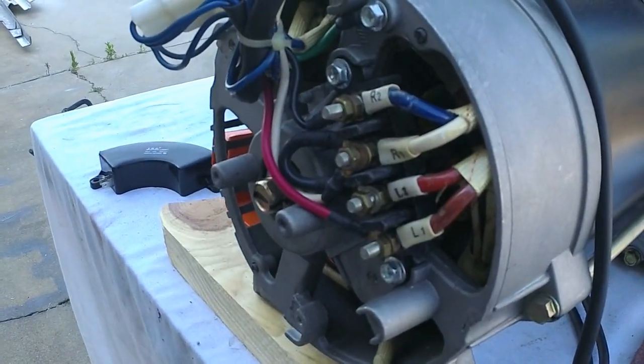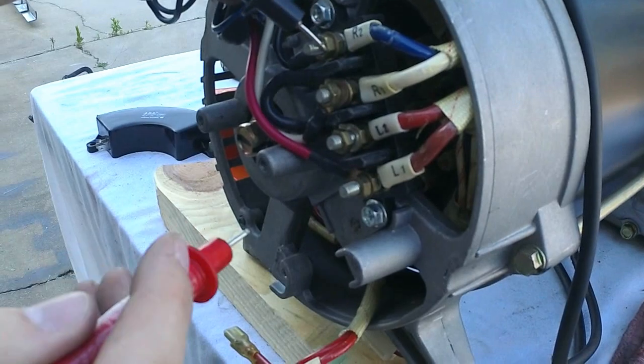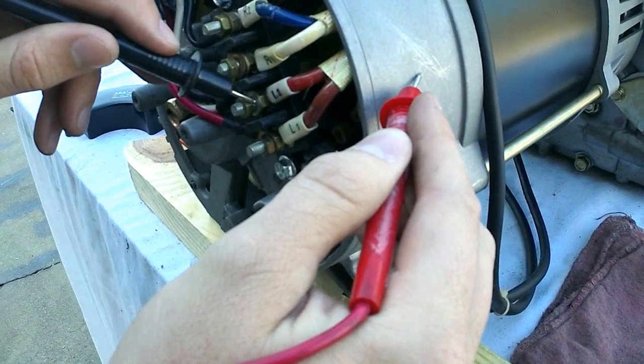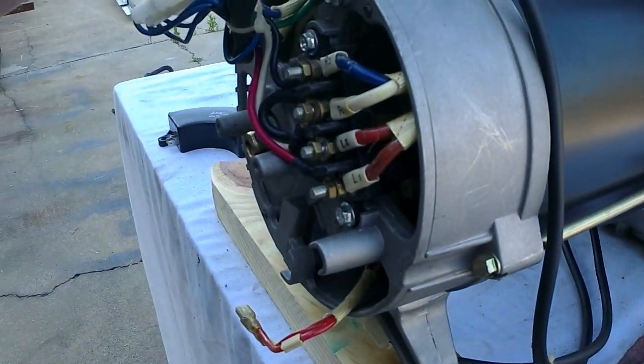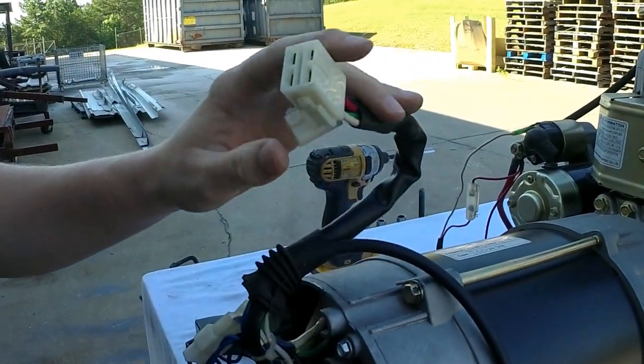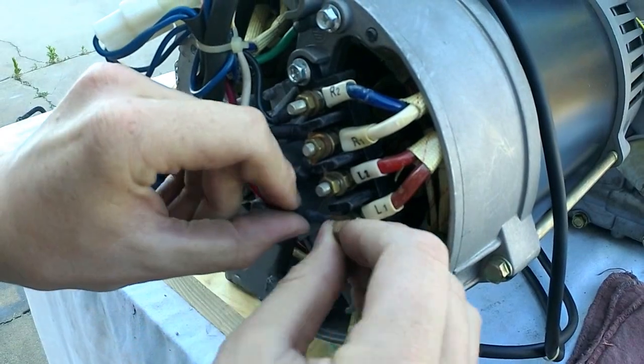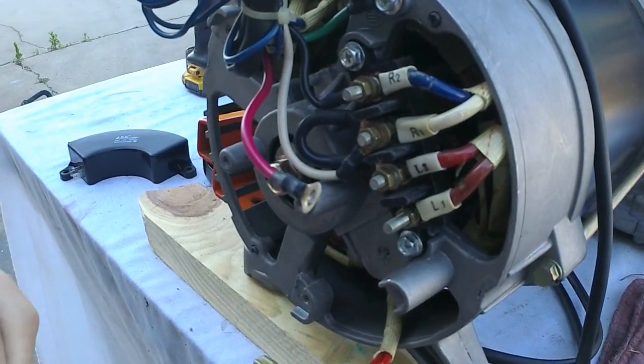Another thing that you can test is between your main leads to ground — you should be showing nothing. You just put one lead on your wire lead and the other one on the ground anywhere on the generator; you should be showing infinite resistance. None of these leads to ground should show continuity — it should always be open. Make sure your panel is unplugged because your panel is grounded, so you will show a ground reading. You can either unplug it with the quick-connect disconnect, or unscrew the 8mm bolts, disconnect your panel wires, and test the way we just did for an accurate reading.